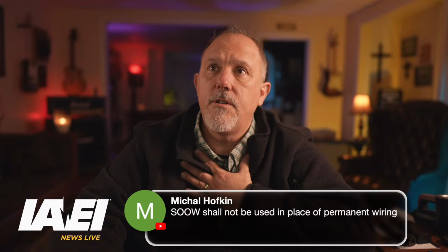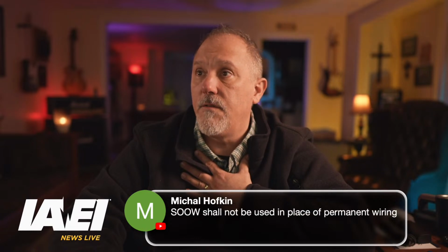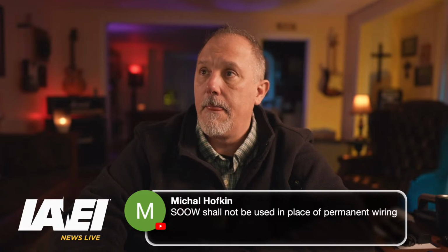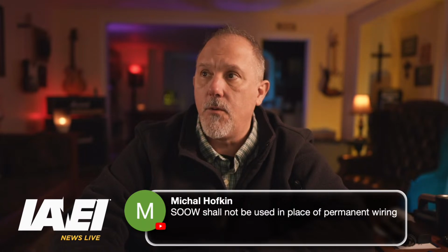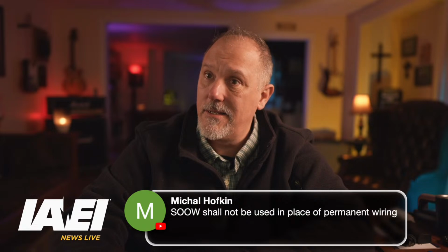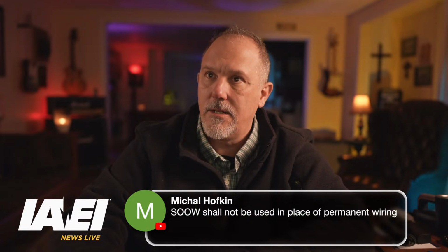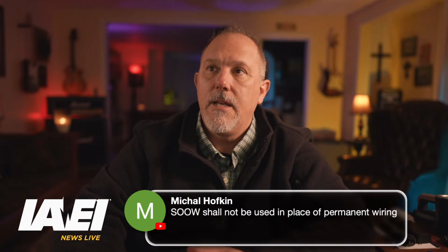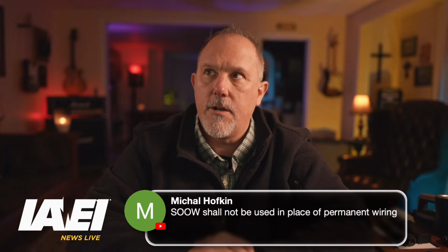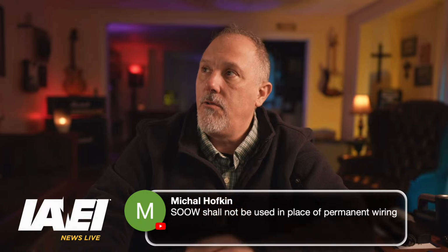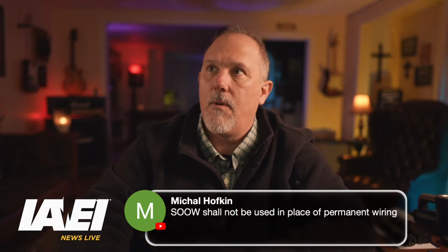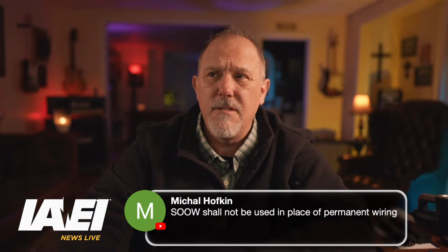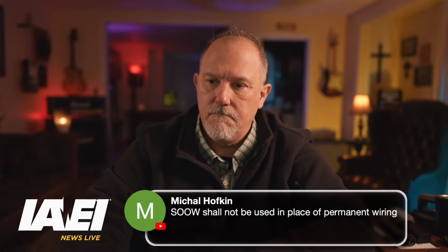Where's 400.10 and 400.12 - that's what I would go to. Because if I come to 400.4, SOOW, I'm hoping, is in that. Yes, it is. It's in Table 400.4 as a flexible cord or cable, and because it's in Table 400.4, your code reference to tell you that you can't put this in permanent wiring is 400.12 - use is not permitted. Make sense? Piece of cake.